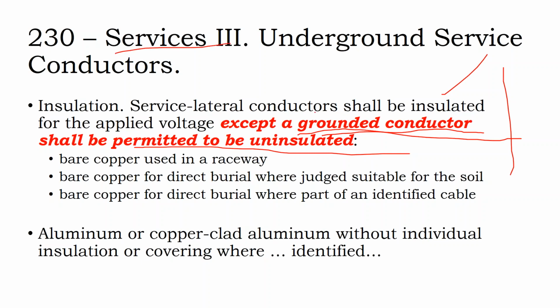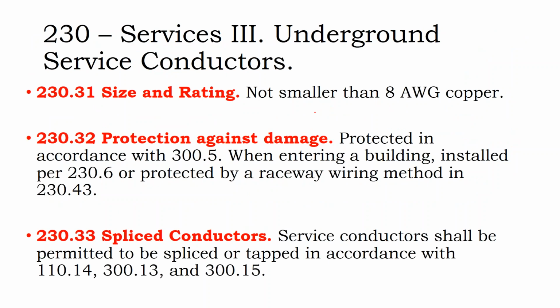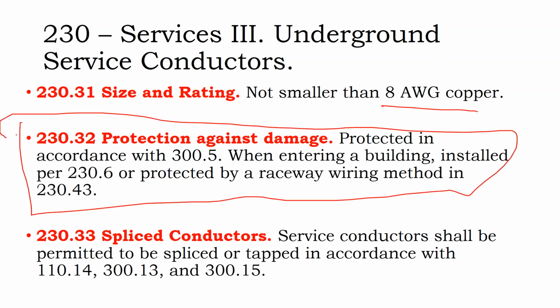And you might see that you're doing a solar design and you're used to running bare number 6 copper up to the rooftop, and all of a sudden you use a different designer and they're saying, no, you've got to have a green insulated conductor and we're running it inside the building. Both are acceptable methods. There are requirements that say not smaller than number 8 in general. Then there are requirements for protection against physical damage.